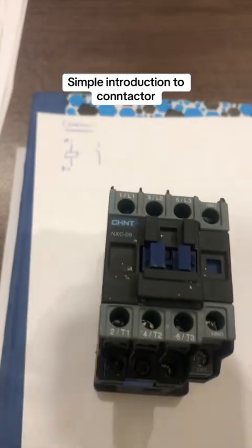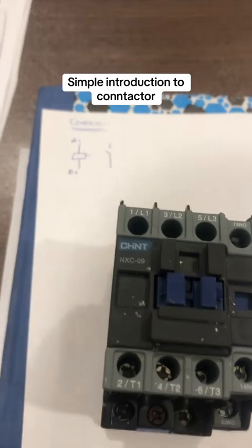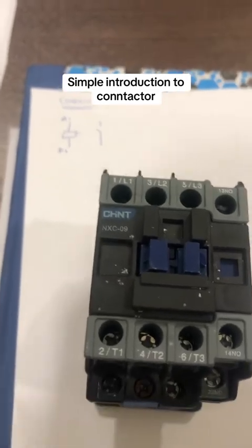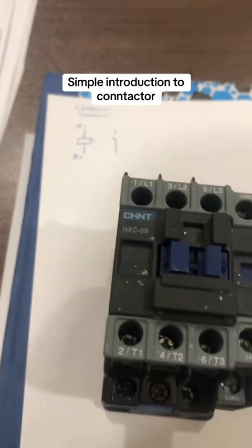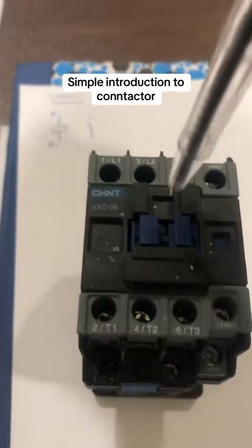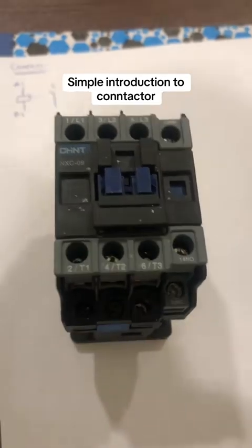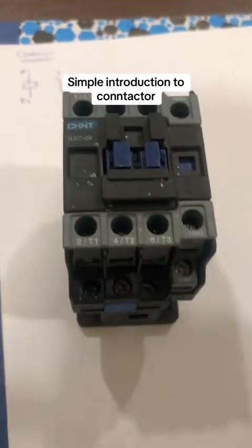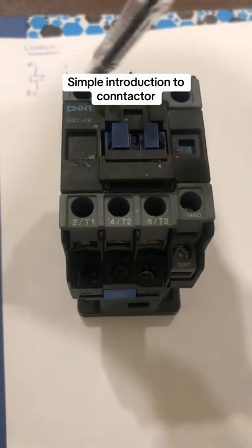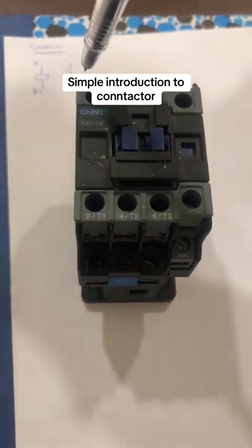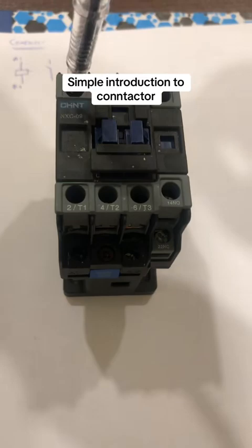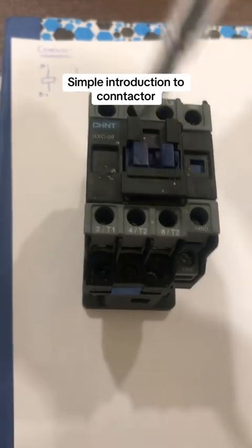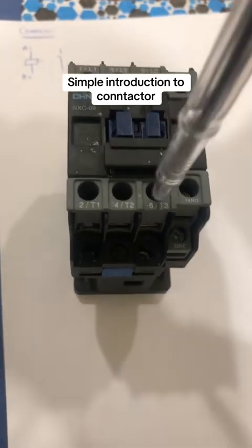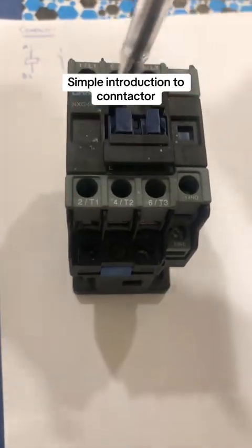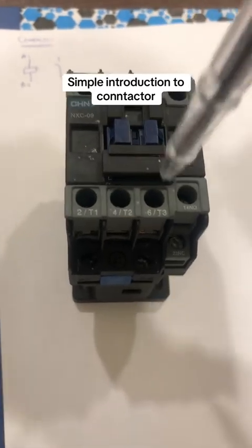Most auxiliary contacts would come with normally closed contacts, that is if you want to make use of normally closed contacts. But for more normally open contacts, you can use the auxiliary contact, which also has a normally open contact on it. But right now we have these three contacts. Mind you, by the time the contactor latches, this contact will connect to this, and this will connect to this. Which means L1 will connect to T1, L2 to T2, and L3 to T3.